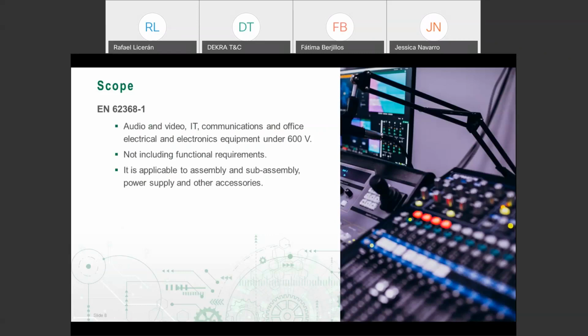In the second edition, we have an exception in order to continue using power supplies which met the old 60950 or 60065 standard. But the last version of this standard is not edition 2. Edition 2 is the version harmonized in Europe, but this year the European Standardization Committee issued edition 3. This edition 3 does not include this exception and is not harmonized yet. Of course, for CE marking, you have to comply with edition 2.